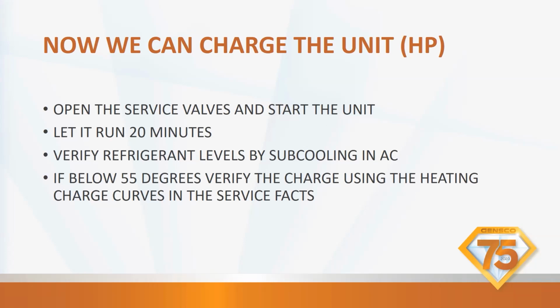So we're going to let it run for 20 minutes. We're going to verify refrigerant levels by subcooling in the air conditioning mode. That's the only way to certify the refrigerant charge for a heat pump. Verify refrigerant levels by subcooling in air conditioning. So if it's too cold outside to do that, then we need to verify the charge utilizing the heating charge curves in the service facts.